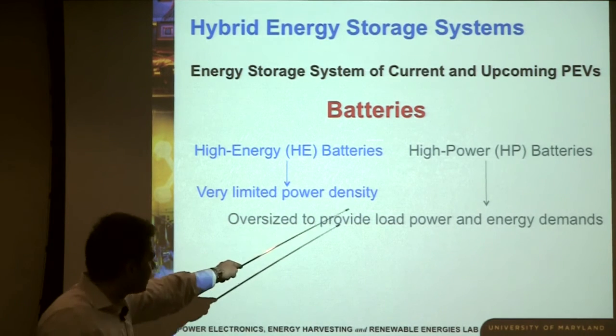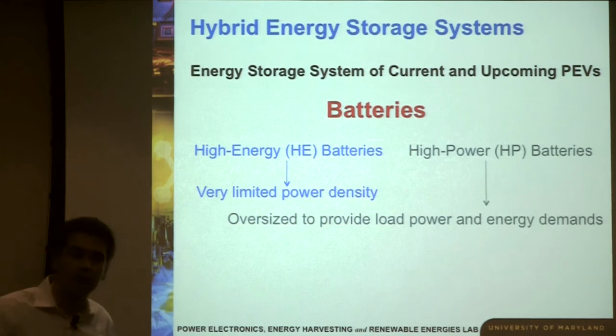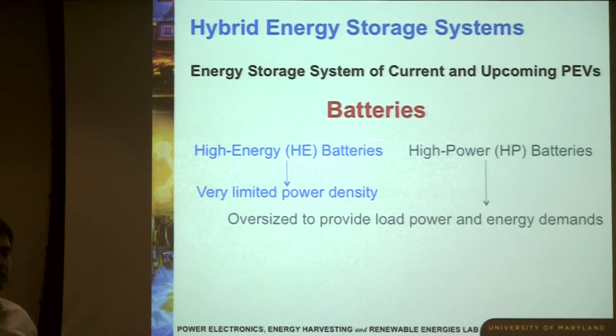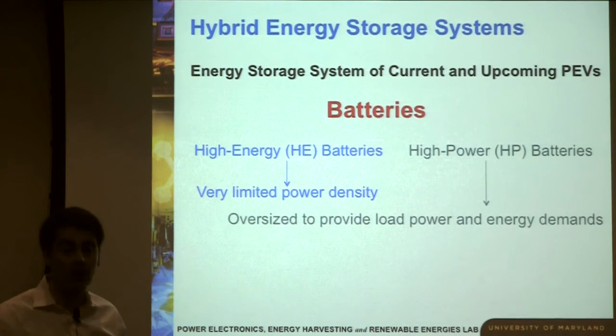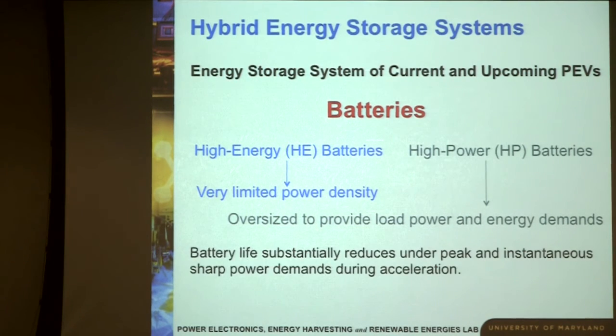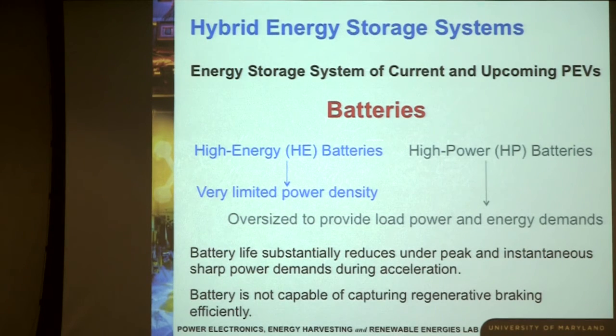But these batteries need to be oversized to achieve high power density, sometimes by up to 4 times according to an article I read, which is significant. In either case, the battery's lifetime reduces significantly depending on the peak power it provides or absorbs. A battery is also not efficient at absorbing energy beyond 80% state of charge, or below about 30% state of charge.